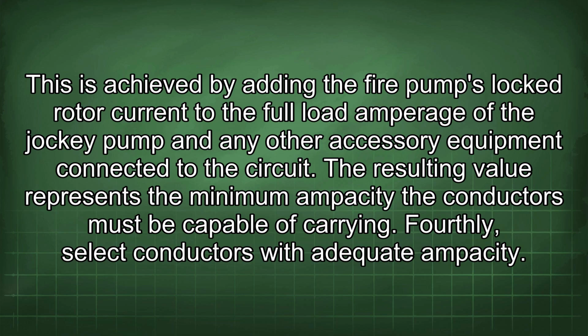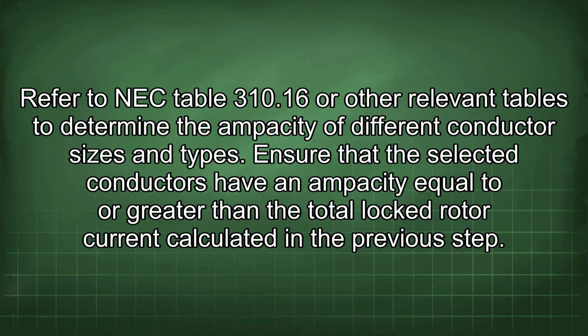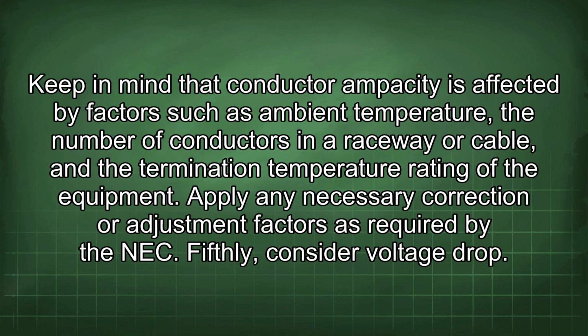Fourthly, select conductors with adequate ampacity. Refer to NEC Table 310.16 or other relevant tables to determine the ampacity of different conductor sizes and types. Ensure that the selected conductors have an ampacity equal to or greater than the total locked rotor current calculated in the previous step. Keep in mind that conductor ampacity is affected by factors such as ambient temperature, the number of conductors in a raceway or cable, and the termination temperature rating of the equipment. Apply any necessary correction or adjustment factors as required by the NEC.